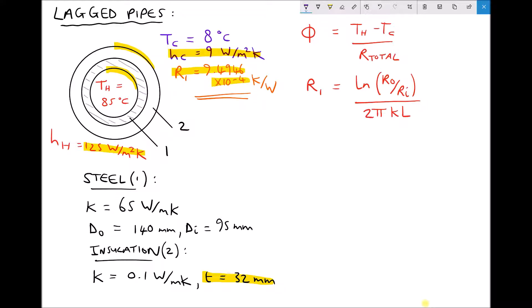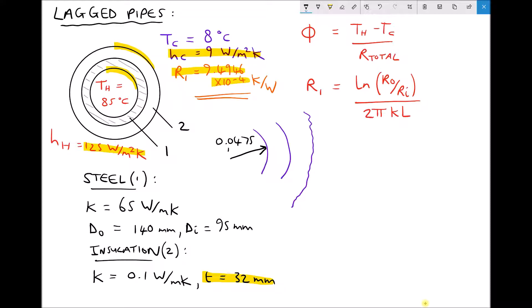The first step, as before, is to produce a sketch indicating our radii in metres. So if we have the centre of our pipe, we have the inside radius of the pipe, the outside radius of the pipe, and the outside radius of the insulation. The inside radius of the pipe is half the inside diameter — the inside diameter is 95 millimetres, so the inside radius is 47.5 millimetres, or 0.0475 metres.